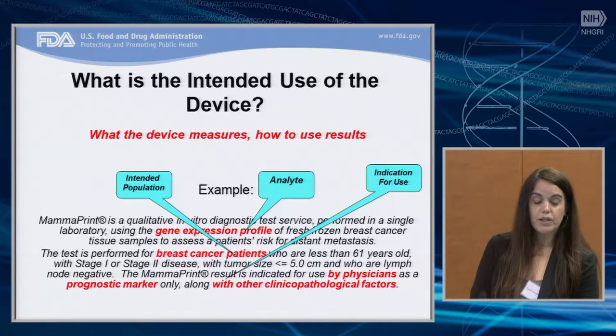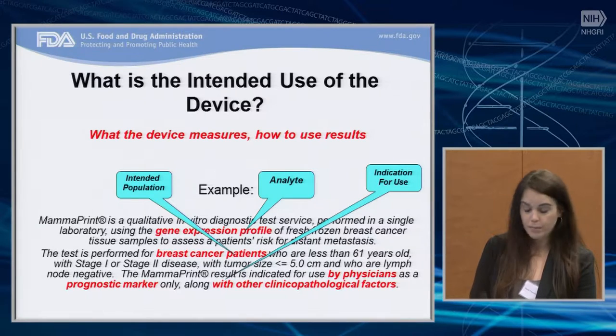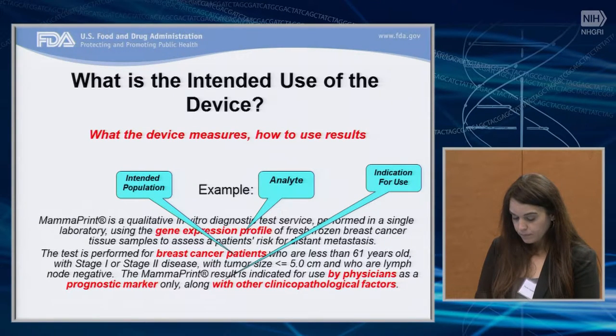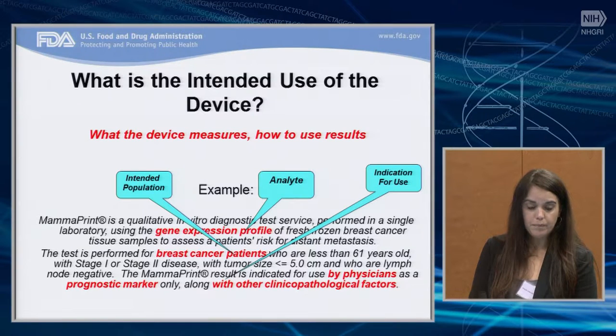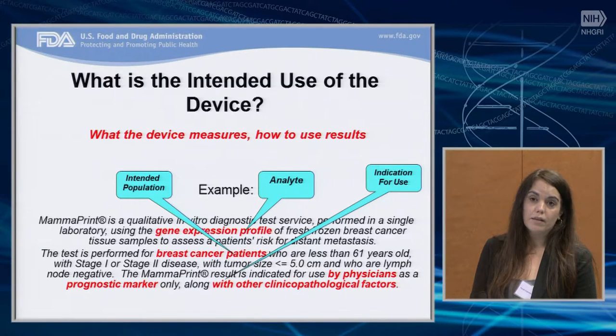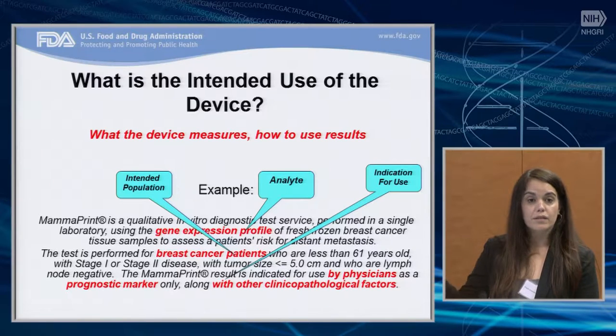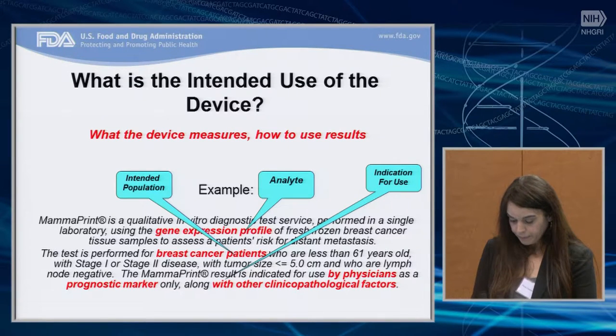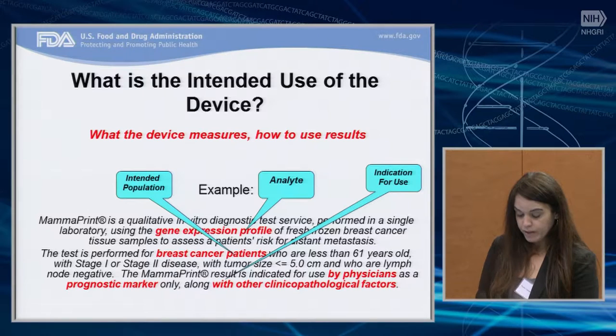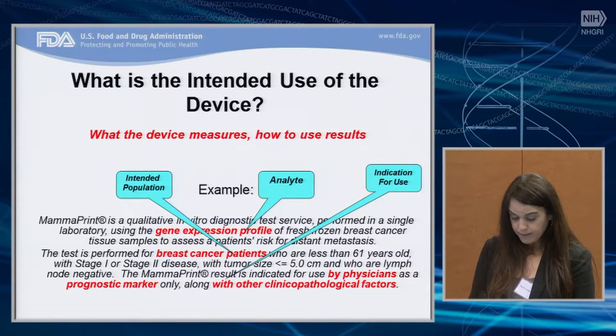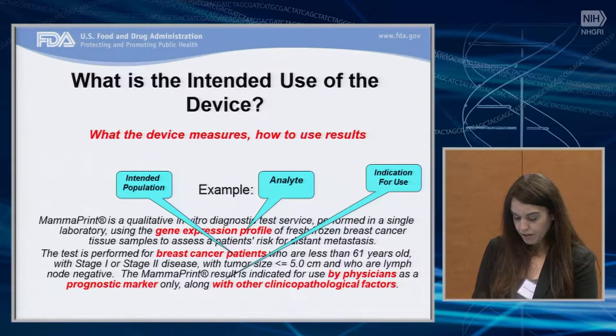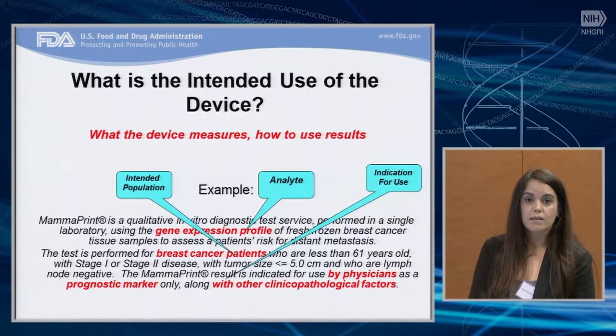It's very important to understand the concept of the intended use as we use the term at FDA. It's really critical to understand when your device may be investigational. When we receive anything from any company or any investigator, the intended use is the first thing we look for, so we can understand what this device is and what it is supposed to do. The intended use explains what the device measures — we call this the analyte. The intended use indicates who is eligible to receive the test — we call this the intended use population. And it also includes the indications for use, that is, how the test result is used.